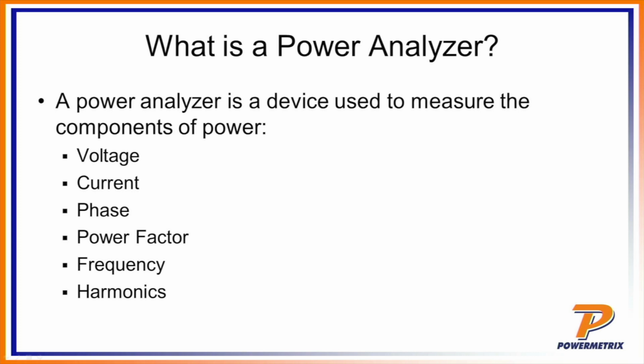Being that this is an AC system, it also has to measure phase. Phase, of course, is the time difference between the voltage waveform and the current waveform. It has a lot to do with power factor. So from the phase, it can derive the power factor. It also measures the frequency of the system. So if you're over in Europe, of course, that would be 50 hertz. Here in the United States, that would be 60 hertz.